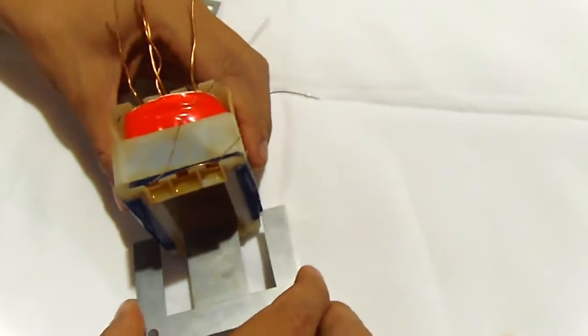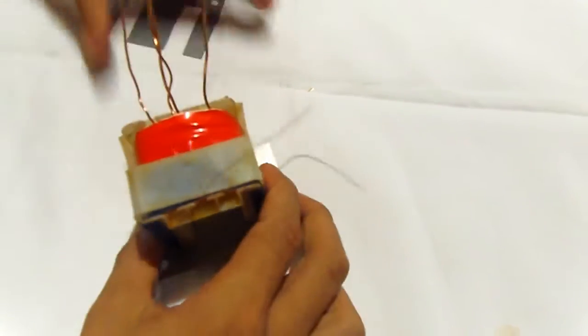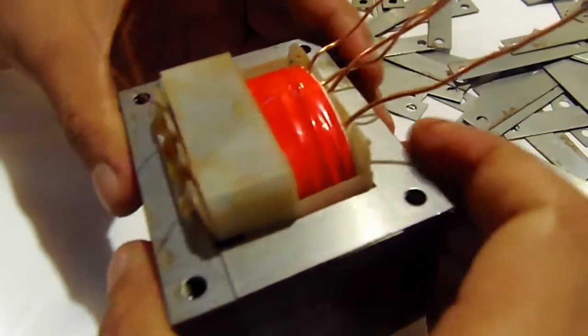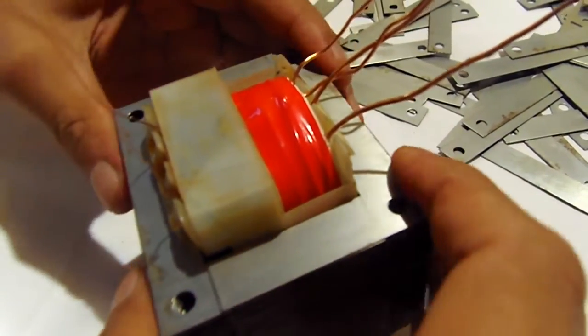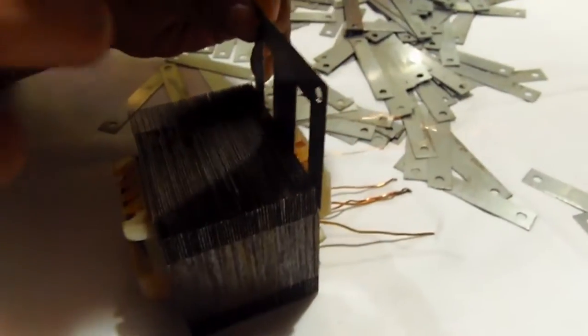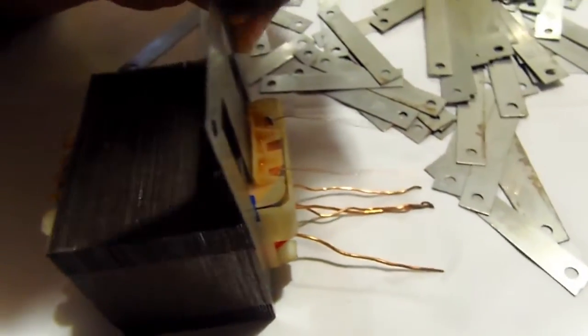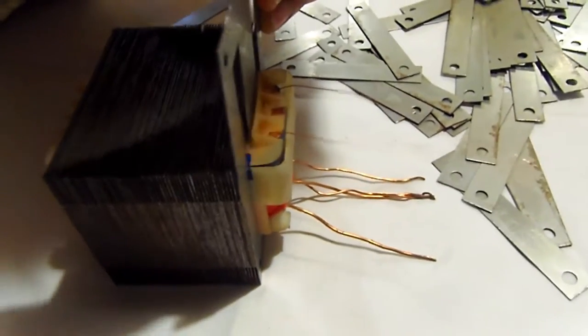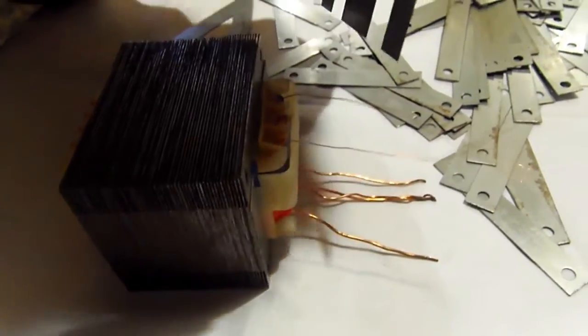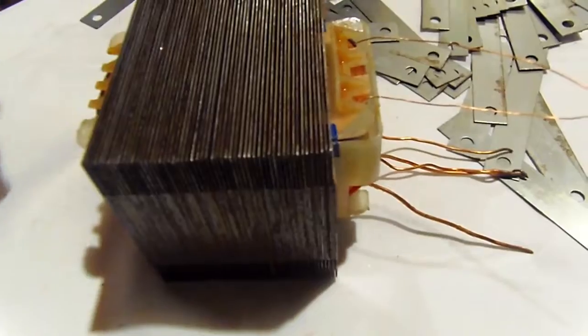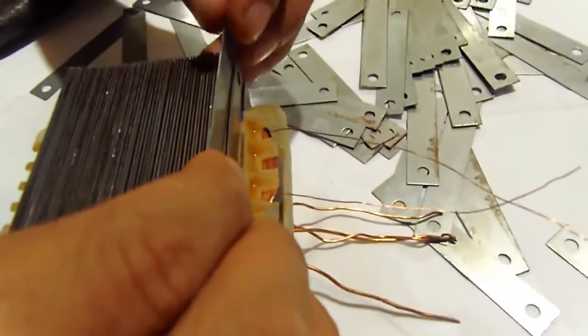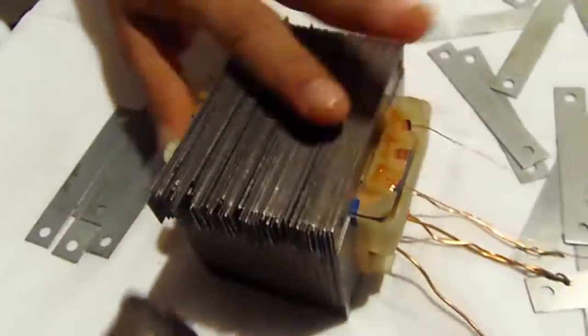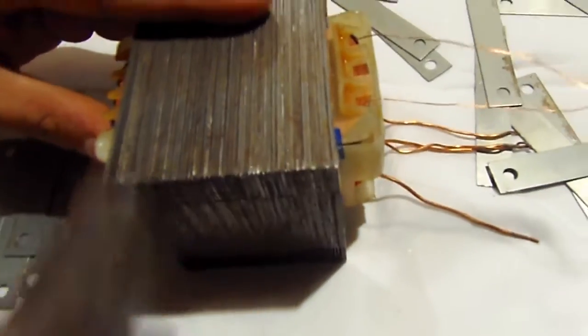Laminating and bracing. The E-laminated steel cores are placed alternately atop each other. The E and I laminations are then pushed through the winding openings so that the butt joints of successive layers are interleaved between flat surfaces in both sides. Make sure that the cores are placed tightly until no further cores can be inserted. The I-laminated steel cores are placed between gaps of the E. Use the hammer to tighten the I cores to the E.